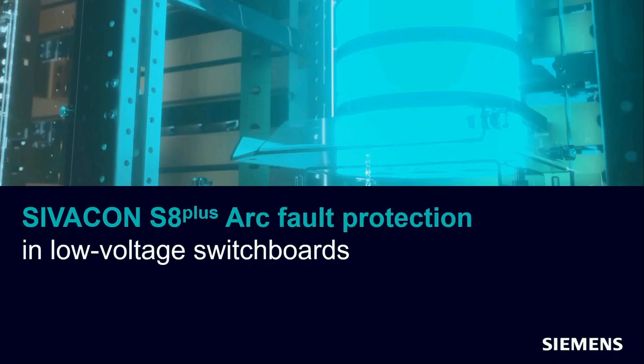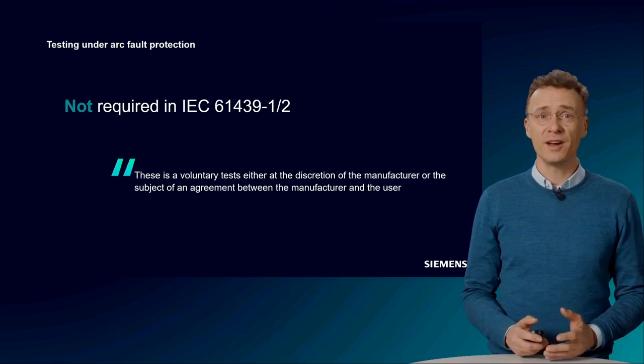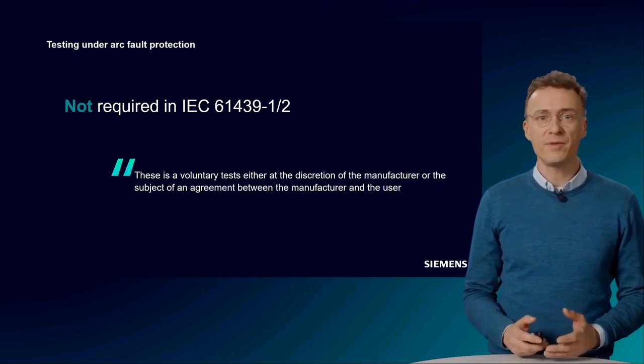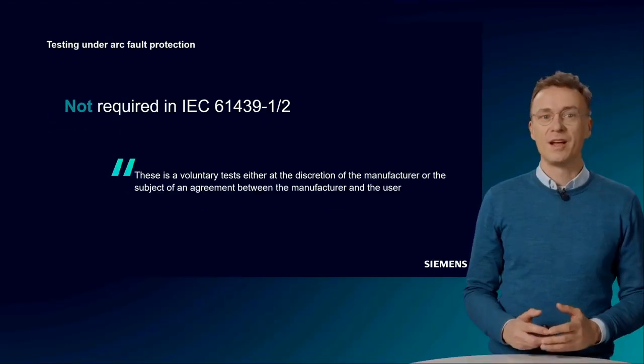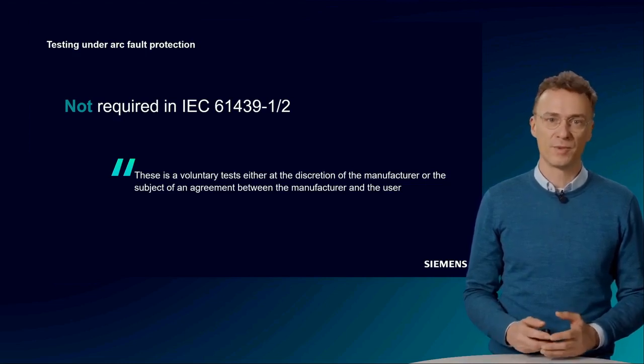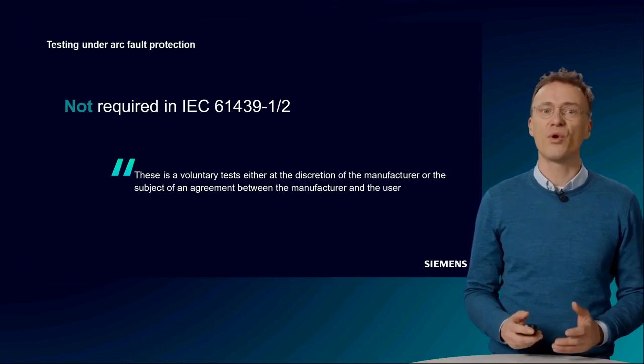Low-Voltage Switchboards are produced in accordance with IEC 61439-2. This regulates topics such as degree of protection, internal separation, and design verification. However, the behavior in the event of an arc fault is explicitly not covered by this standard. The requirements for arc fault behavior are regulated in a technical report, which is not part of IEC 61439-2.